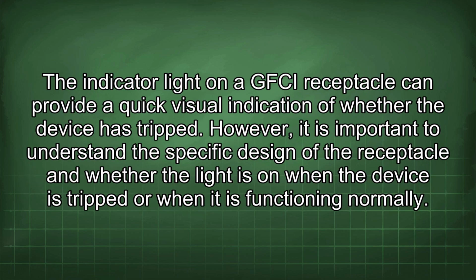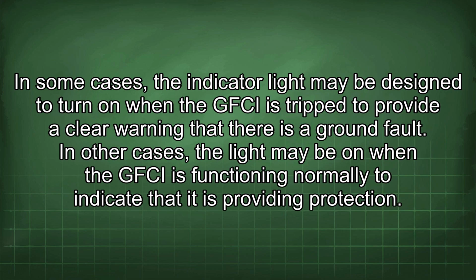The indicator light on a GFCI receptacle can provide a quick visual indication of whether the device has tripped. However, it is important to understand the specific design of the receptacle and whether the light is on when the device is tripped or when it is functioning normally. In some cases, the indicator light may be designed to turn on when the GFCI is tripped to provide a clear warning that there is a ground fault.